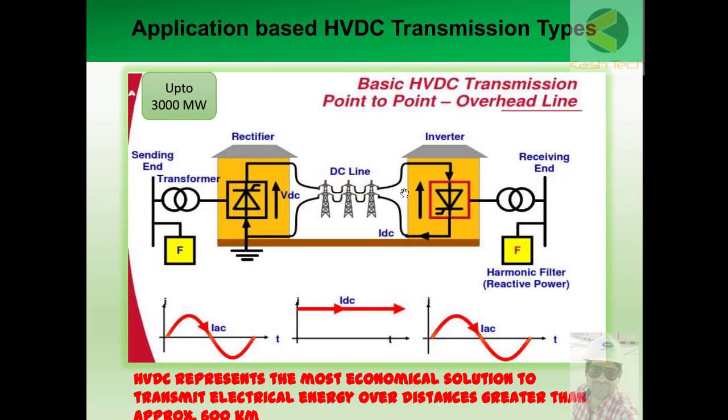HVDC presents the most economical solution to transmit electrical energy over distances greater than approximately 600 kilometers. If the line length is 600 kilometers or more, it becomes economical — as a general thumb rule — to connect two different networks using HVDC instead of HVAC. This is especially true when you need to supply more than 3000 megawatts over such distances.